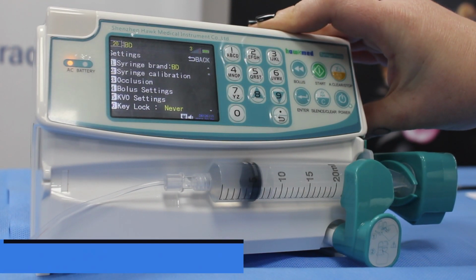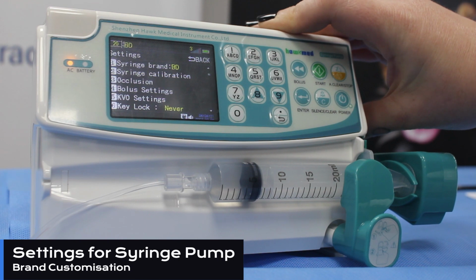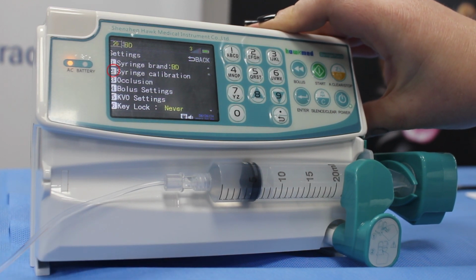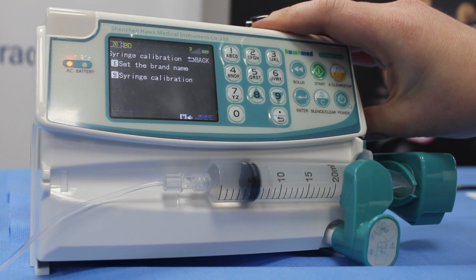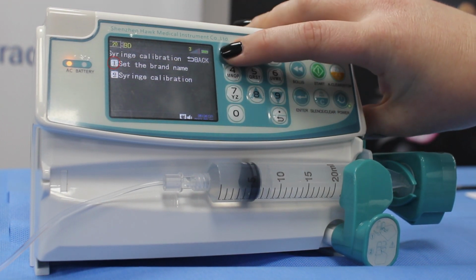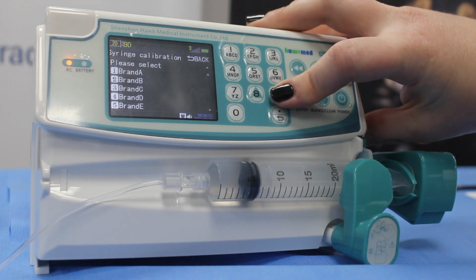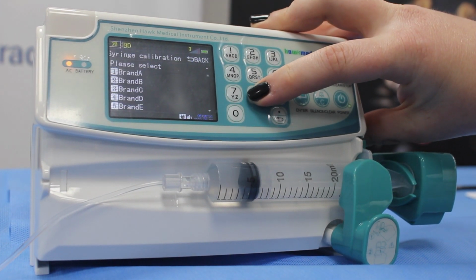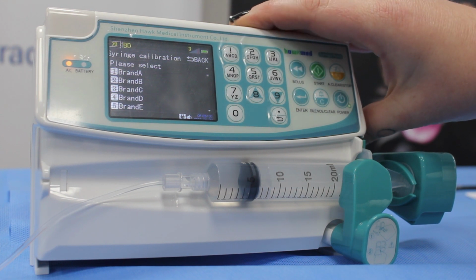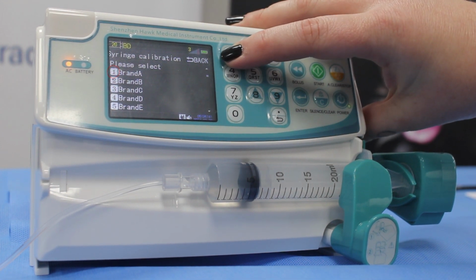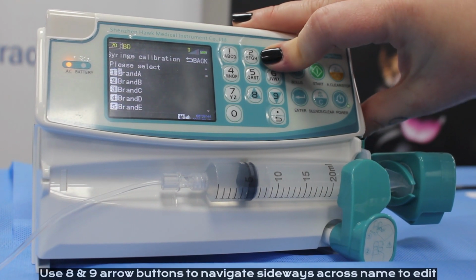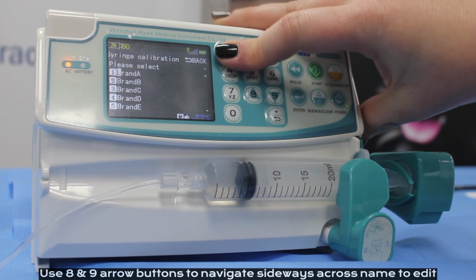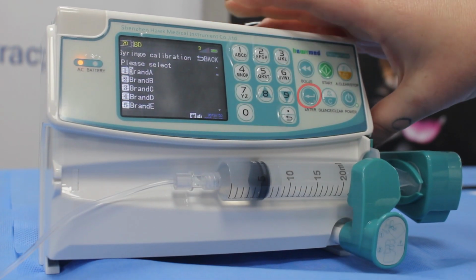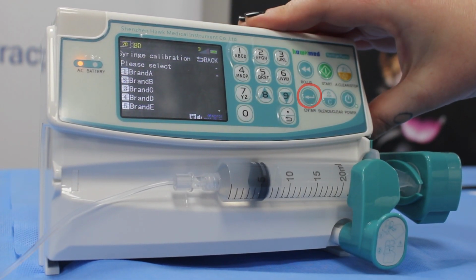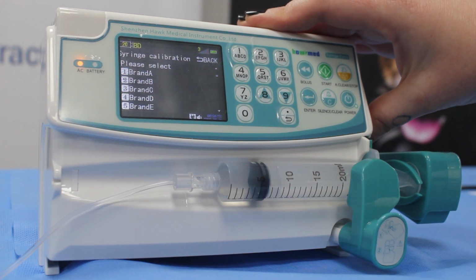To calibrate the syringe brand so that we can use them on our pump, we'd use syringe calibration under number 2. Here we can set our brand names using number 1, scrolling down with the 8 and 9 as required, and then again pressing the corresponding number to adjust your text. So here we could change the brand if we decided to. So we'll pop it just back to B for us, and again enter to confirm.